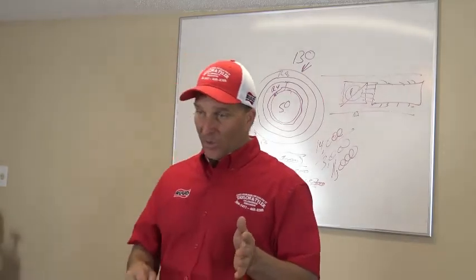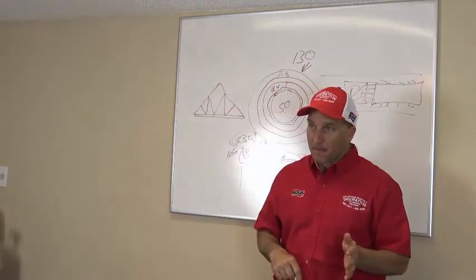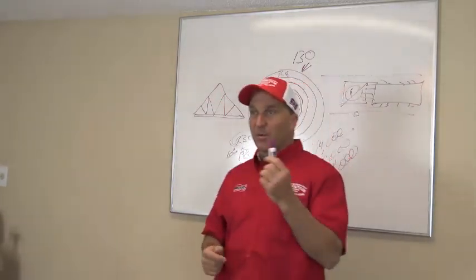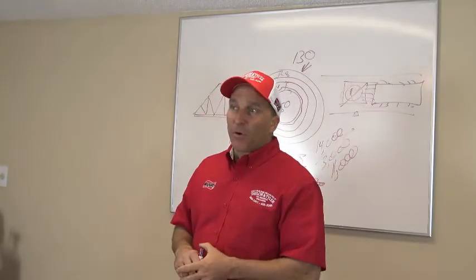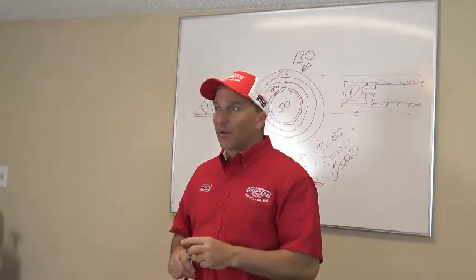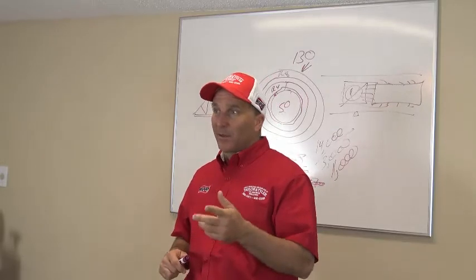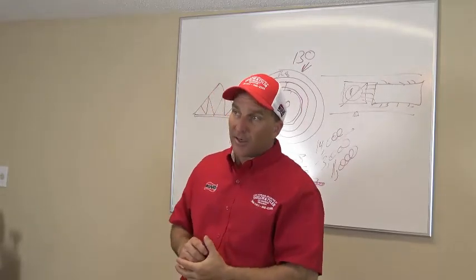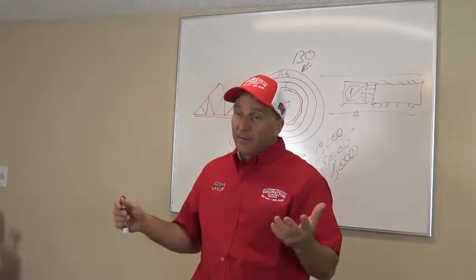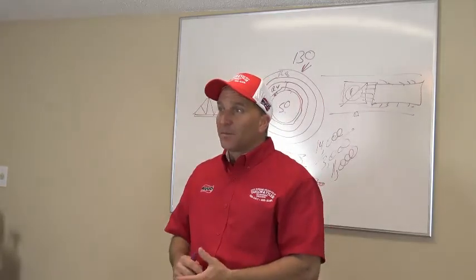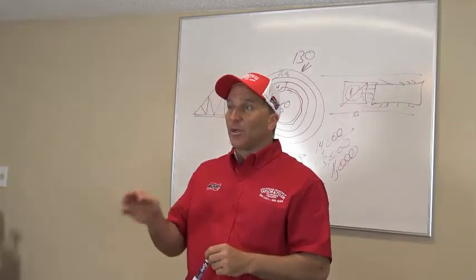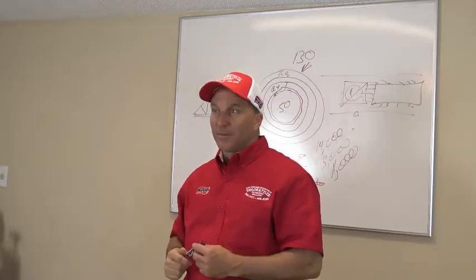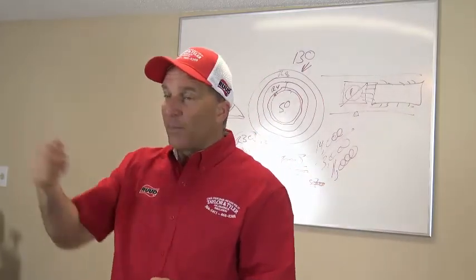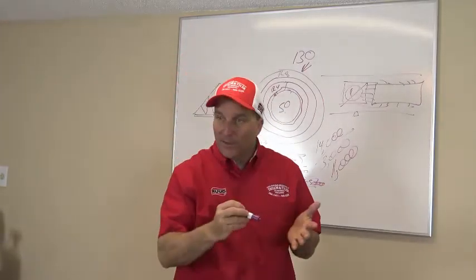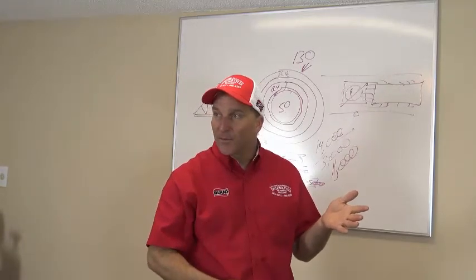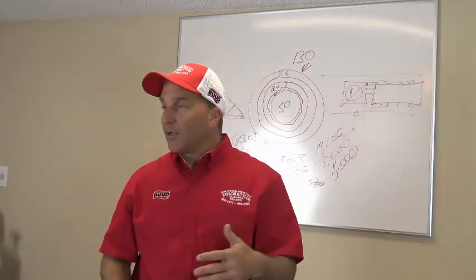One year later, customer calls back. I went back out there and I said, I remember this house. Your evaporator coil's rotted out, your drain pan's rotted out, your drain line's probably clogged again because you got water on your ceiling, I see. And I said, you ready to go ahead and replace the system? And sure enough, they actually had the original invoice on their mantle. And I saw it and went over there and picked it up and I rewrote everything that I wrote again. Okay?